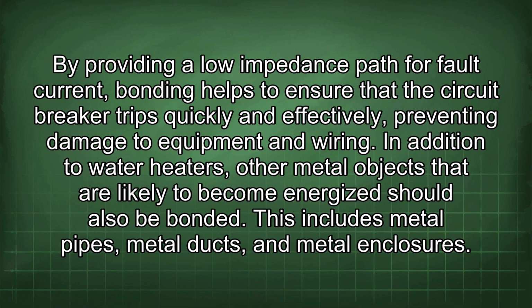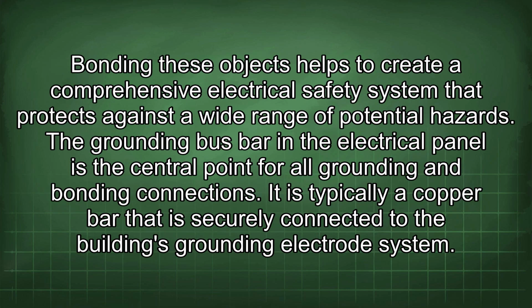In addition to water heaters, other metal objects that are likely to become energized should also be bonded. This includes metal pipes, metal ducts, and metal enclosures. Bonding these objects helps to create a comprehensive electrical safety system that protects against a wide range of potential hazards.